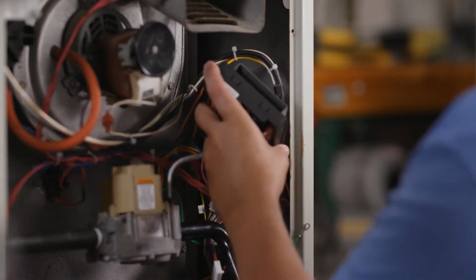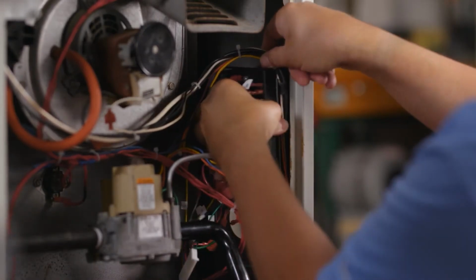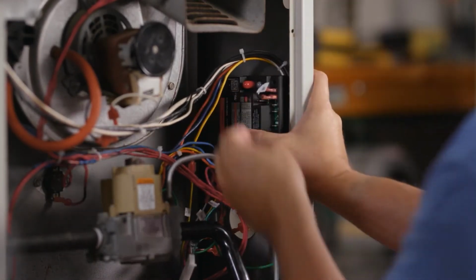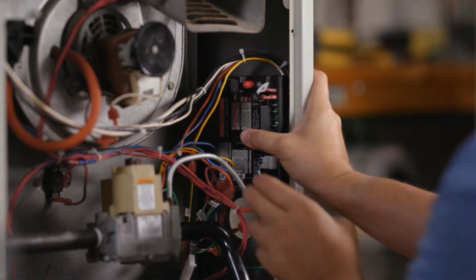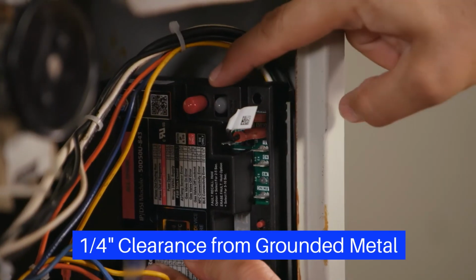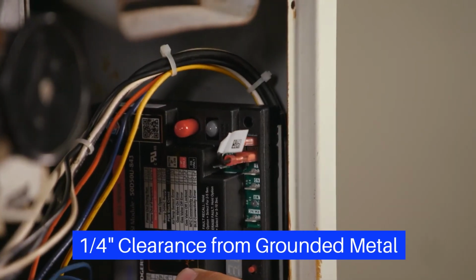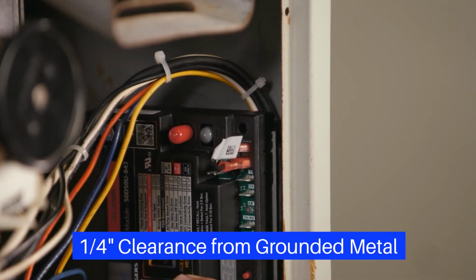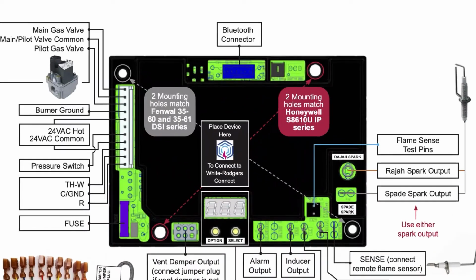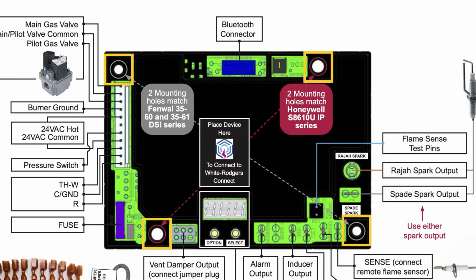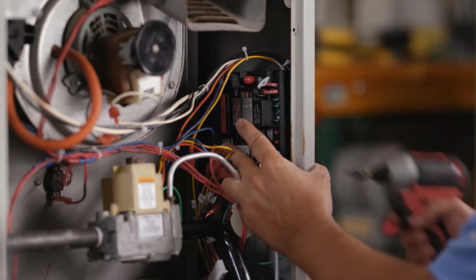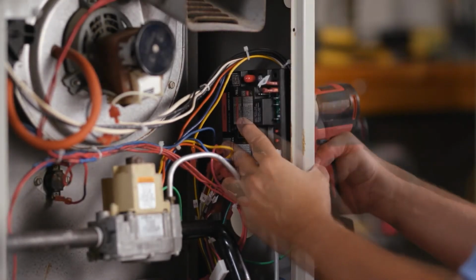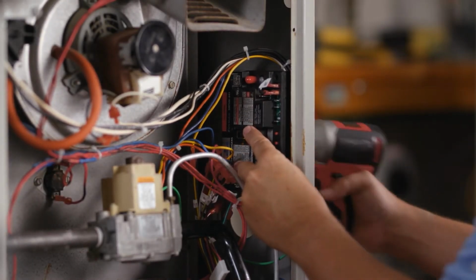The module can be mounted in any orientation. Select a location that will not damage, obstruct, or place stress on the terminations or harness. Ensure there is a clearance of 1/4 inch between the sides of the control and the grounded metal. There are 4 mounting holes located toward the corners of the module. Utilize the 2 that match the existing module. Mount the 50D50U-843 in the unit using the mounting holes and supplied screws.